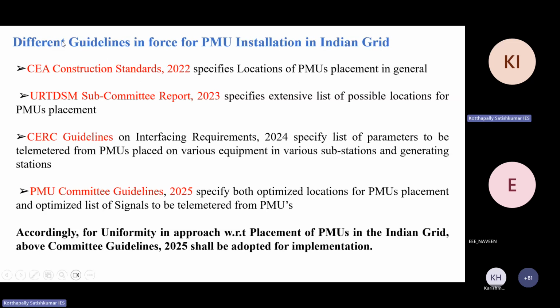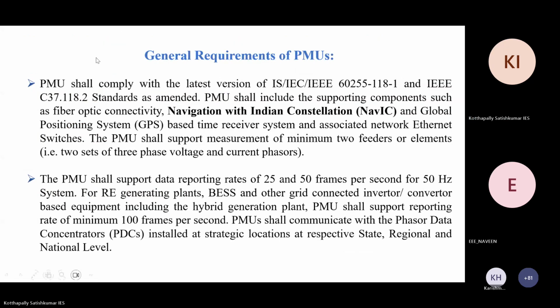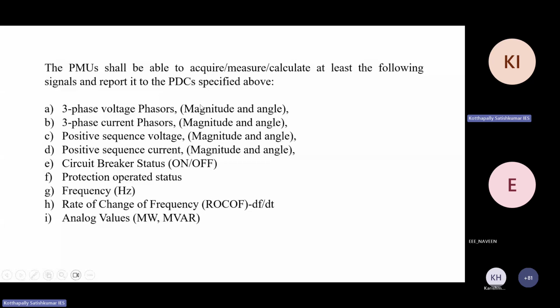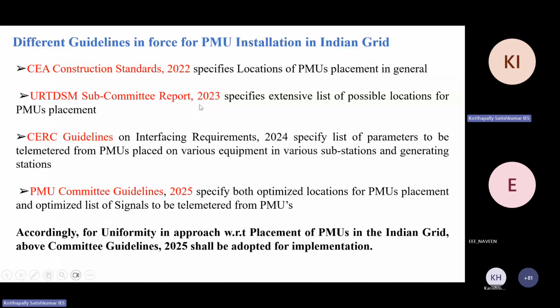Now we'll go through the different guidelines for PMU installation in the Indian grid. One issue is that we have the CEA construction standards of 2022 which specify PMU locations, the URTDSM subcommittee report of 2023 which gives a list of possible PMU placement locations, and CERC guidelines which specify exactly what parameters are to be telemetered from PMUs at various substations and generating stations.